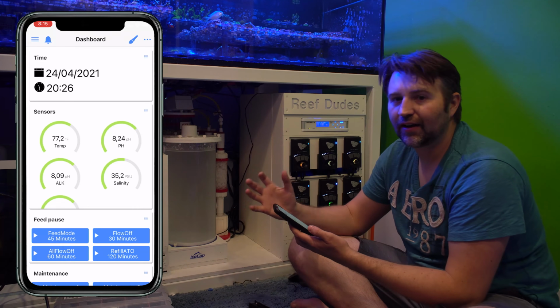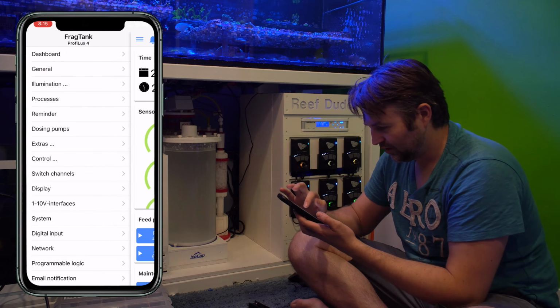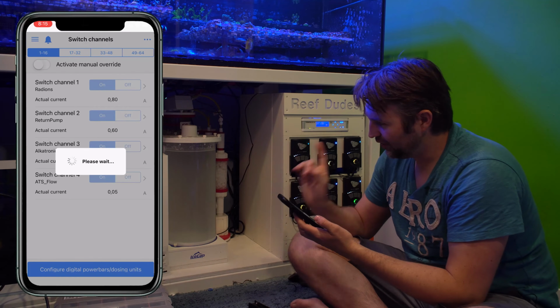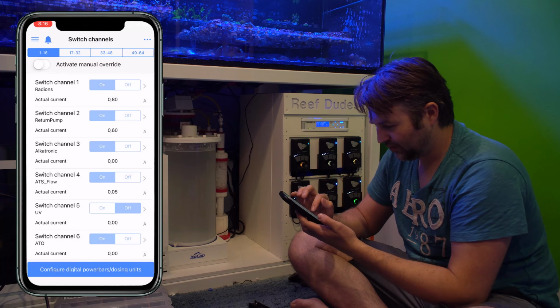6.67 to 6.73, okay, so we've got the pH valve set up. Now we need to set our outlet to be pH controlled. So if we go into our switch channels, the one that the UV used to be on is the one that I hooked up the solenoid to. So switch channel 5 for UV.